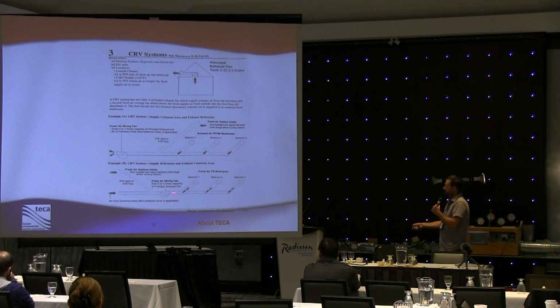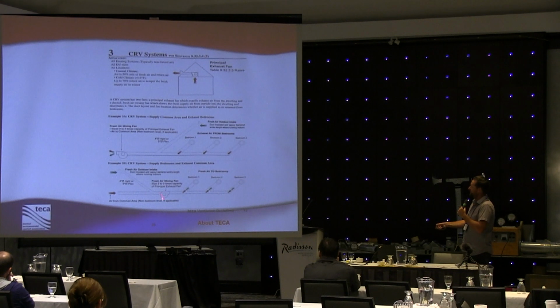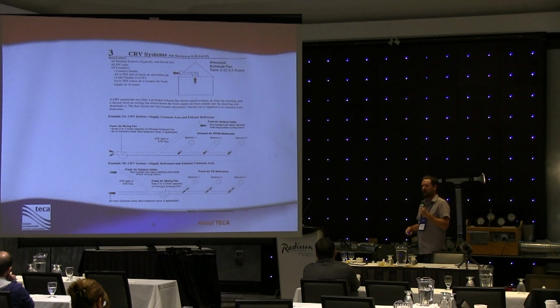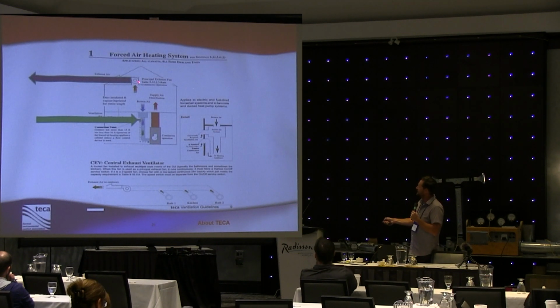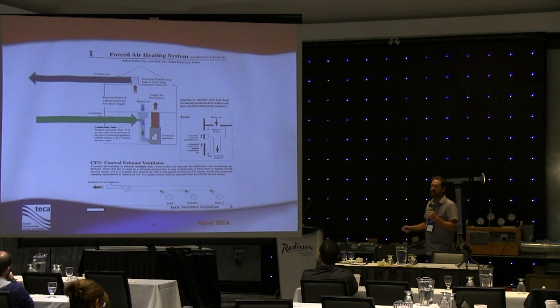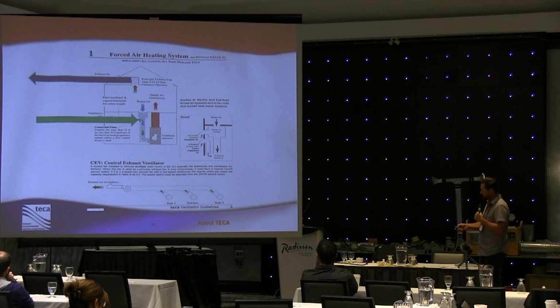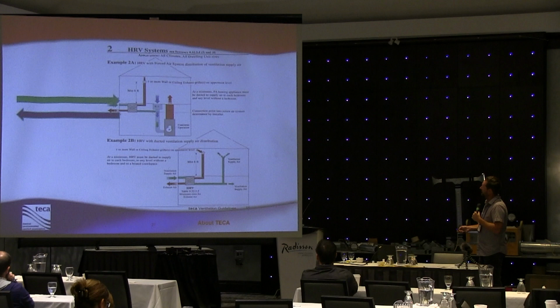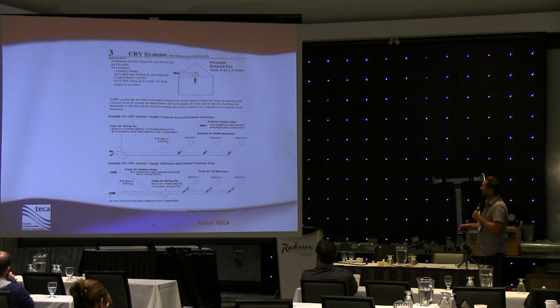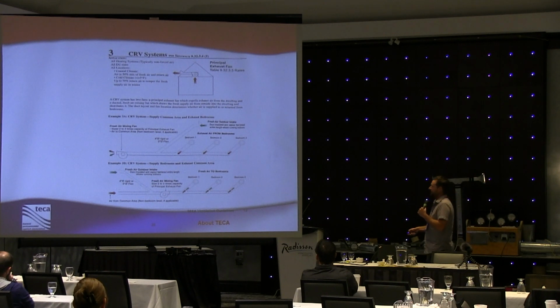On a coastal climate, this fan has to be sized 2 times larger than our principal exhaust fan. Now, the principal exhaust fan shown here is the same type of setup as we have in our System 1. Okay, our System 1, if we go back, has a principal exhaust fan that's continually running to exhaust stale air out of the building. So it's the same setup. We're exhausting out of the building, but we need to bring the fresh air back in. So what we're doing is we're setting up a dedicated fan that's going to do that. On the coast, this fan is going to be 2 times the capacity of this fan.